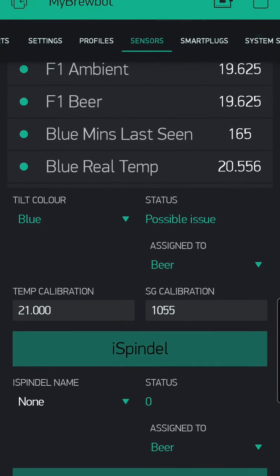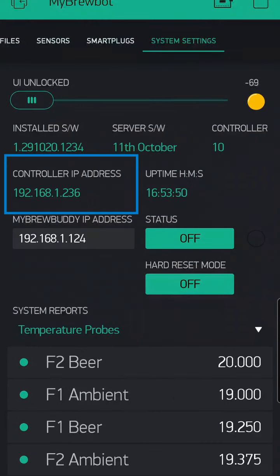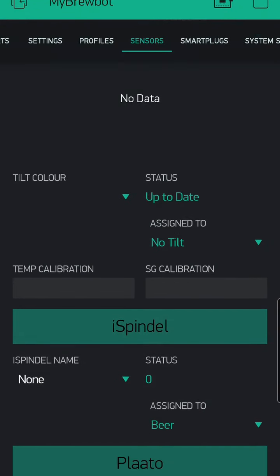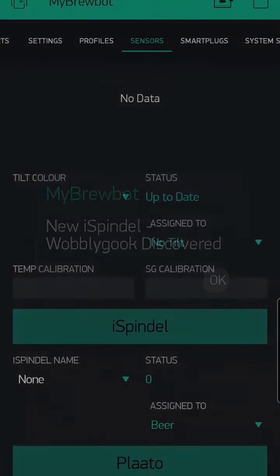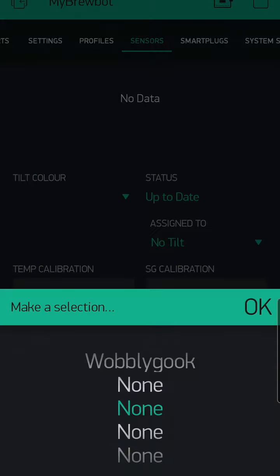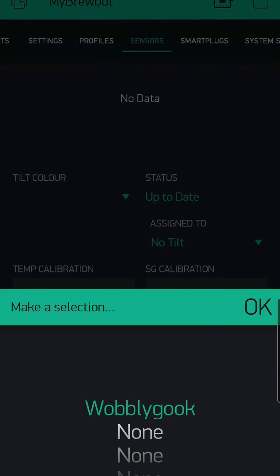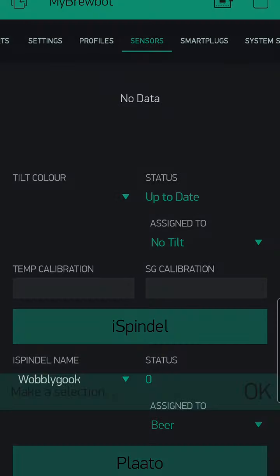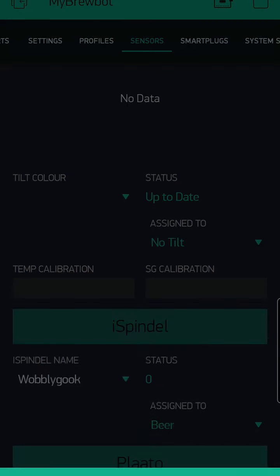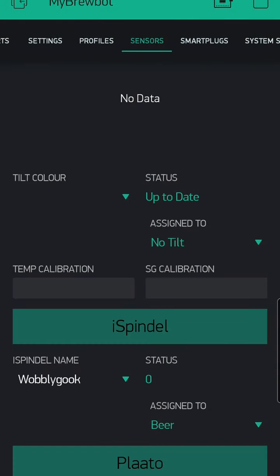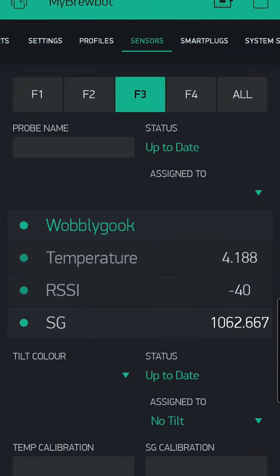iSpindel devices. Set up your iSpindel so that it points to the controller's IP address. There is a separate video showing how to do this. Once the iSpindel has been set up, it will start to send data to the controller. Once the controller receives an iSpindel message, it will send you a screen notification to tell you it has found a device. Select the fermenter tab you want the data sent to, allocate the iSpindel and assign it a task.